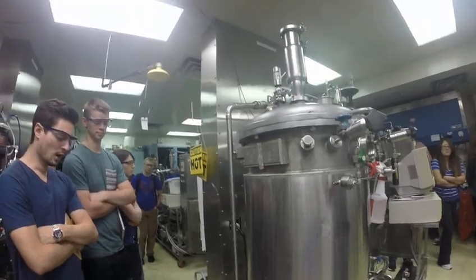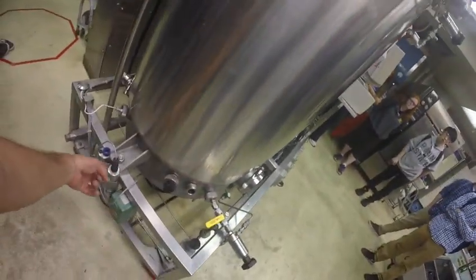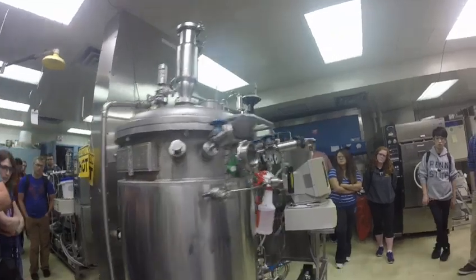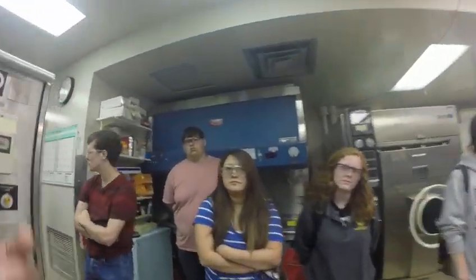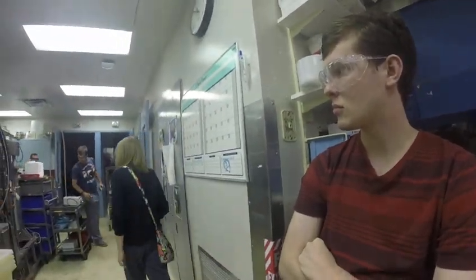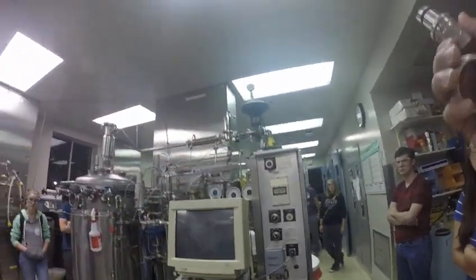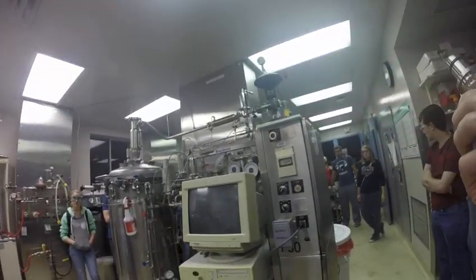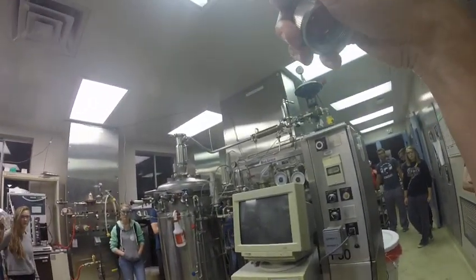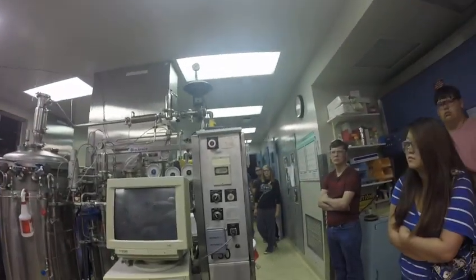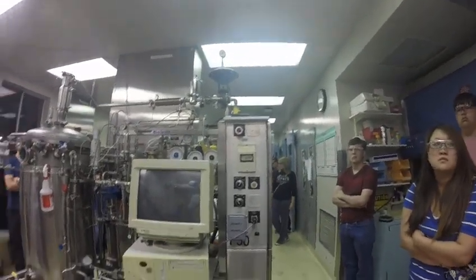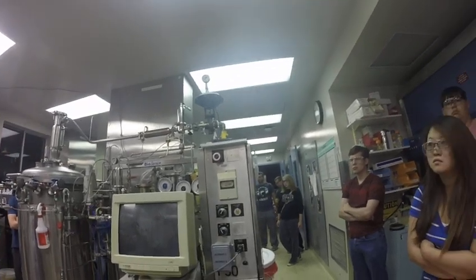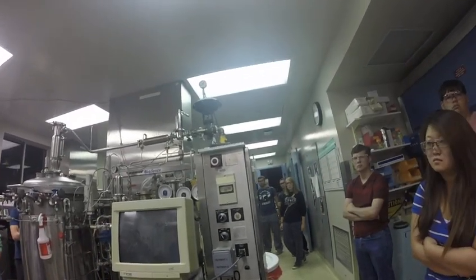And in fact, if you take a look on the bottom side here, you'll see that these are actually transducers. There should be some on the back side of that unit there. You see on the back side of that unit there's two little canisters. Those are just the transducers. But what this does is it gives a little bit of uniformity, right? If you want to be a manufacturer of a new probe, you just need to make it go through a 25 millimeter Ingold port and talk to that transducer there, and then anything you get, you can slap it in there and it'll talk through that system to the controller.